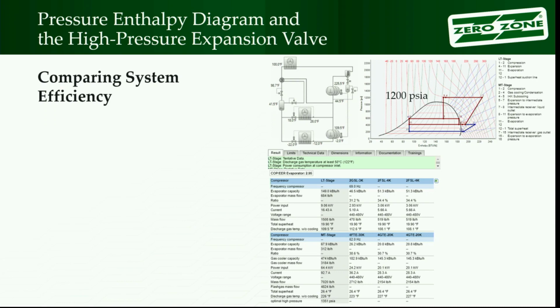So I'm out there and I know a lot more about it. I force that valve open to drop its head pressure because that's what I've learned my whole life. And I dropped the pressure down to 1200 psi. Everything's great. What do I have now? Do I have more flash gas or do I have less flash gas? So what do you think is going to happen to the cooling effect of that system? Down. It's going to go down.